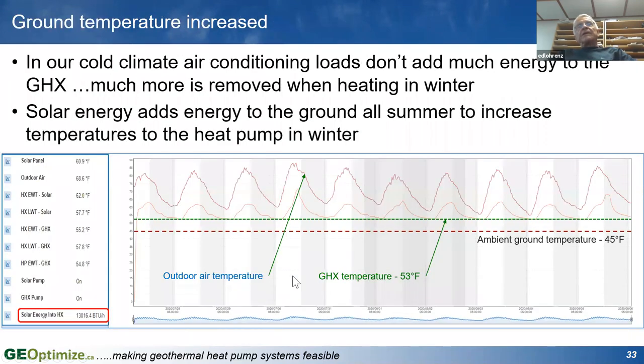So what I found is that the ambient ground temperature in Winnipeg is about 45 degrees Fahrenheit. Right now, the ground temperature is about 53 degrees Fahrenheit, and I've never seen it that high before. So I'm basically using that to balance the amount of heat that's going into the ground versus how much is coming out. A couple of years ago, the temperature in my ground loop that my heat pump saw was less than 24 degrees Fahrenheit. By this winter, I'm expecting it to be increased by about 4 or 5 degrees.